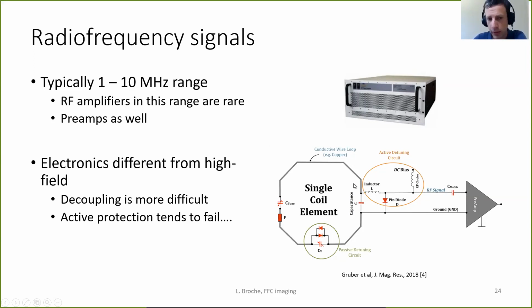For instance, when you make RF coils, the elements that are used to make the image, one of the strategies to decrease the scan time and increase the image quality is to use coil arrays. And coil arrays require protection circuits to make sure that the electronics doesn't burn when the transmit pulse is being sent. And this electronics is typically, as you see in this figure here.